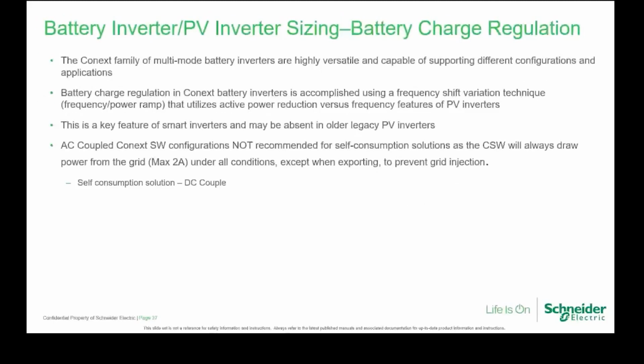We support different configurations and applications. Battery charge regulation is accomplished using a frequency shift, as we've been talking about before. Basically, it's frequency-power, a function that utilizes active power reduction versus frequency. It is a feature of smart inverters, but it may be absent in legacy PV inverters. Some of the older PV inverters, when they see the grid frequency changing, can either do a partial curtailment or just drop off. Once the frequency gets too high or too low, some of those legacy ones will just turn themselves off and not ramp down.